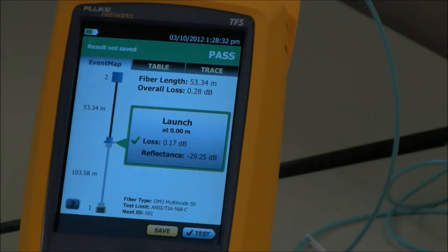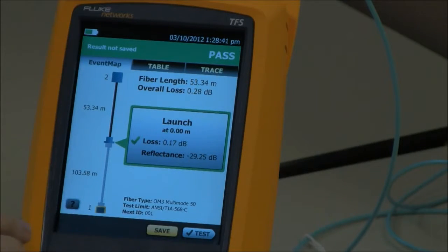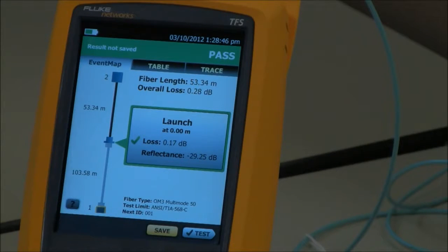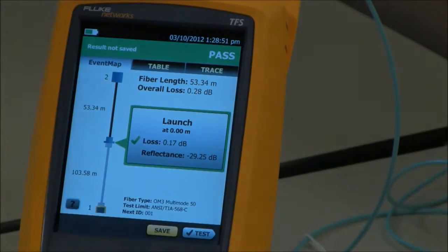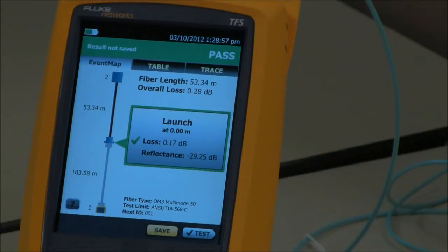Our loss is 0.17 dB and our reflectance is minus 29.25 dB. But hold on — you need to be careful here. The 568C standard does not currently specify reflectance as part of your test limit, so you will never fail on reflectance.